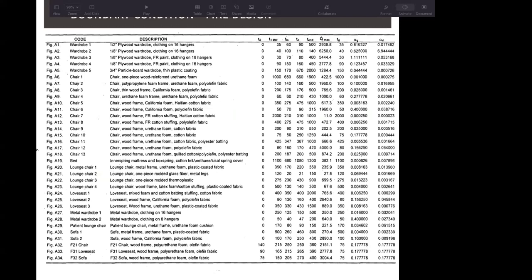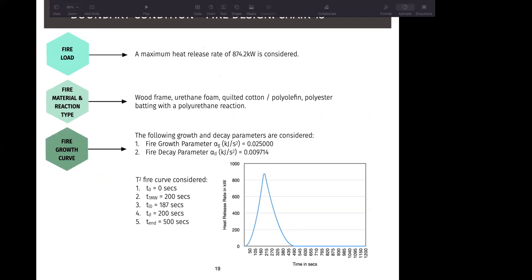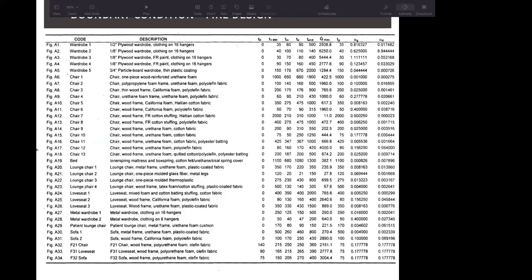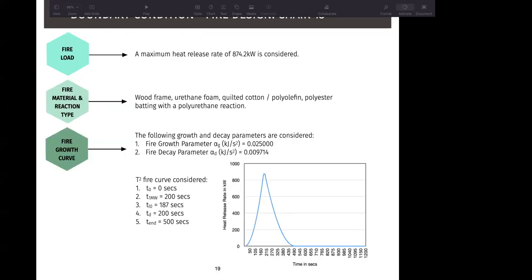So if now we are looking at, say, chair 13, which has a material of wood frame, urethane foam, quilted cotton, polyolefin, or polyester batting with polyurethane reaction, and it has a maximum heat release rate of 874.2 kilowatt. The fire growth parameter and decay parameter has already been given in this particular sheet, the last 2 columns. And as per that, we can then calculate the t-square fire curve. So in this instance, when the fire starts at 0 seconds, it would attain a 1 megawatt fire load at 200 seconds. It would attain a fire load of 874.2 kilowatt, which is the maximum heat release rate, at 187 seconds. It will have a flashover at 200 seconds, which means all the fuel has now been depleted and there will be a decay time.